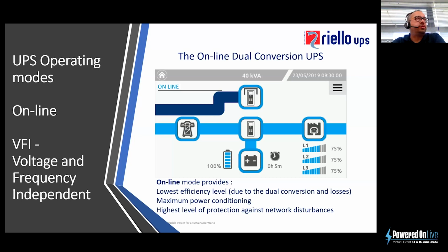On the screen, you can see a typical diagram of an online dual conversion UPS system. On the left, you have the input supply. On the right, you have the load. At the bottom, you have the batteries, which are there to support the UPS system when the main supply fails. And at the top, you have the bypass line, which is used for things like maintenance, issues, alarms, faults, and so on.